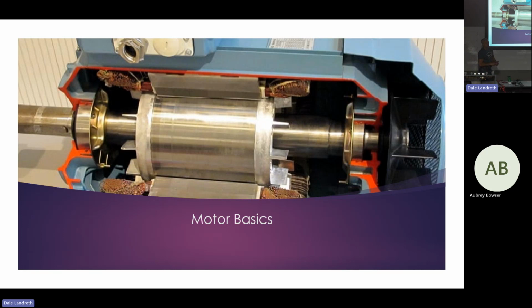So it's telling us that because the resistance is so low when voltage is first applied, the inrush current is high. How high is it typically? What's the number? 7 times? I've usually seen 5 to 7, I usually say 6. So 6 times the full load amps. If full load amps is 10, what should my inrush current be? 60, whatever number you want to use. So 6 times, it'd be 60 amps. Immediately I'm pulling 60 amps on this motor.